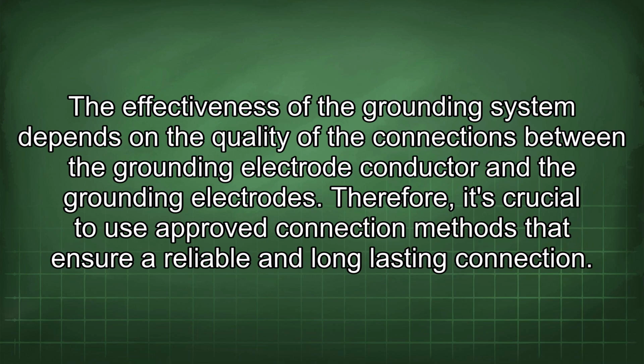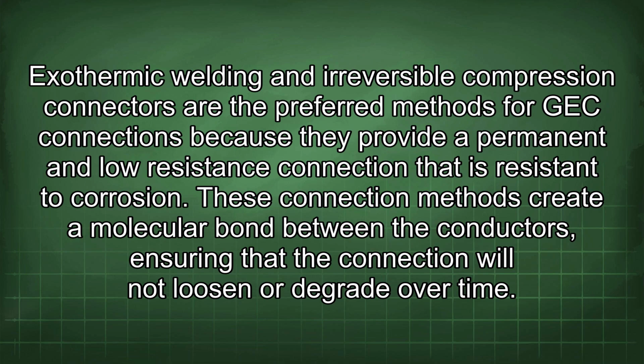The effectiveness of the grounding system depends on the quality of the connections between the grounding electrode conductor and the grounding electrodes. Therefore, it's crucial to use approved connection methods that ensure a reliable and long-lasting connection. Exothermic welding and irreversible compression connectors are the preferred methods for GEC connections because they provide a permanent and low-resistance connection that is resistant to corrosion.